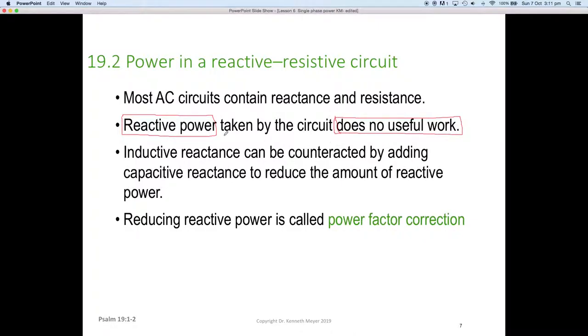Inductive reactance can be counteracted by adding capacitive reactance. Remember we said they were at 180 degrees from each other. Inductive reactance was at 90 degrees from unity and capacitive reactance was at 90 degrees the other way. By reducing the amount of reactive power, we just add some capacitive reactance and it counteracts the inductive reactance. If we manage to do that by reducing the reactive power, it's called power factor correction.